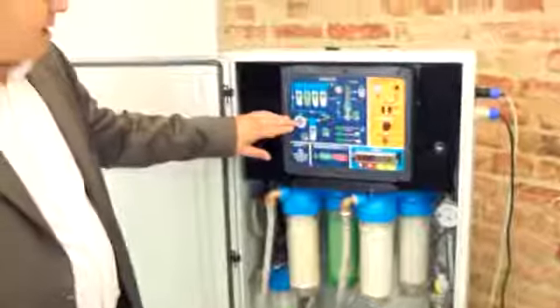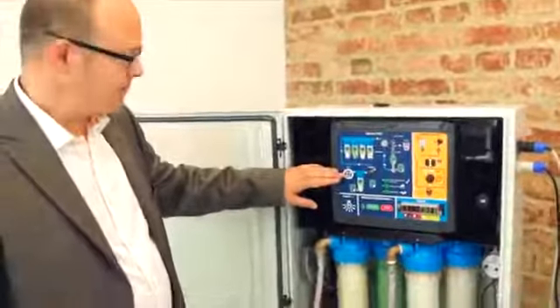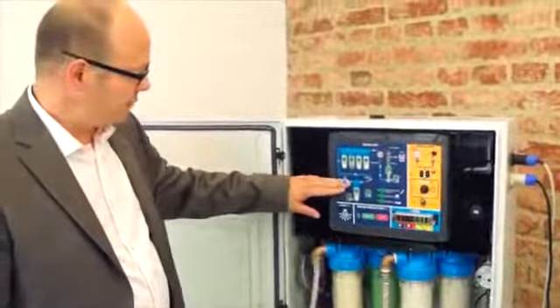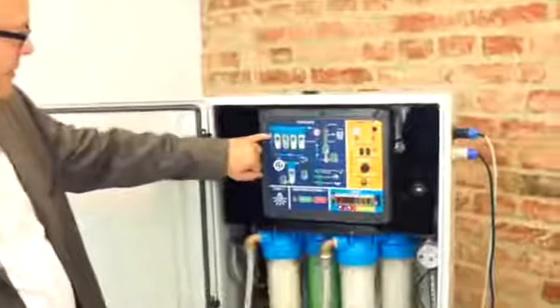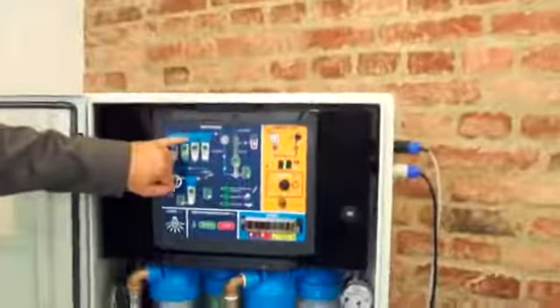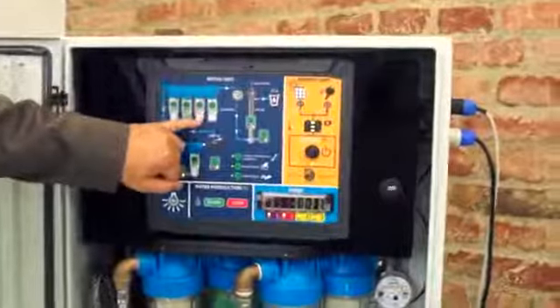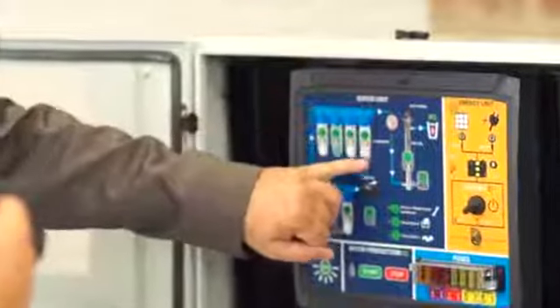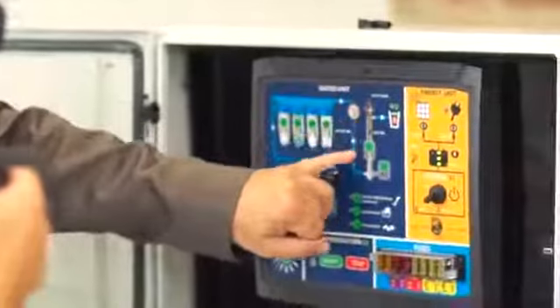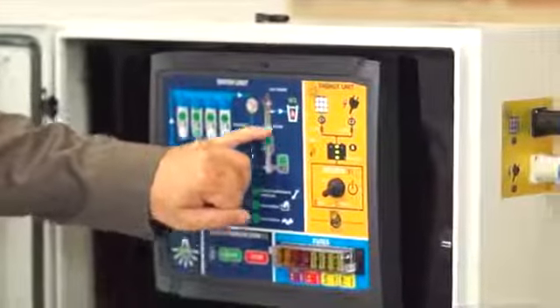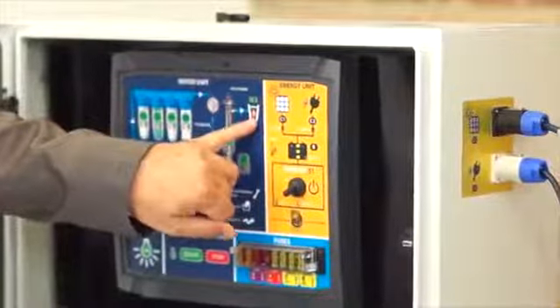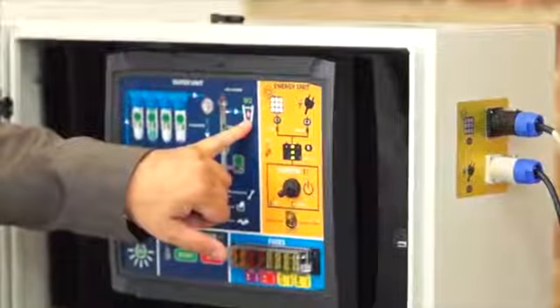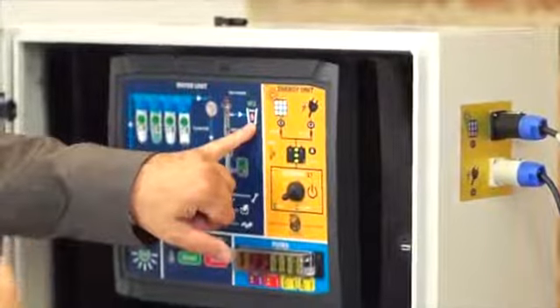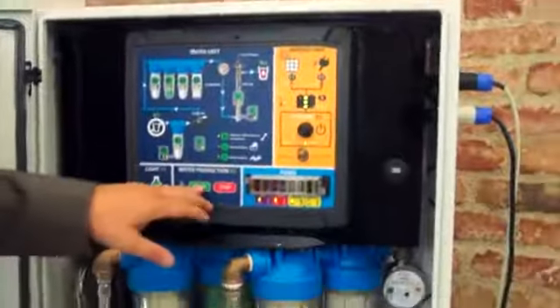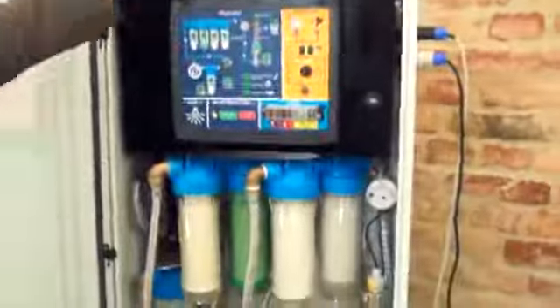On this layout you see the connection for the raw water, it is the germ-infested water. It enters the first filter, goes through the pump, then flows through the first fine filter, followed by the carbon filter, the last fine filter, and the magnesium filter. The water volume is measured by the water counter before it enters the UVC unit. Here the indicator shows that currently it is not disinfected and we should not drink it yet. We can start the machine now.